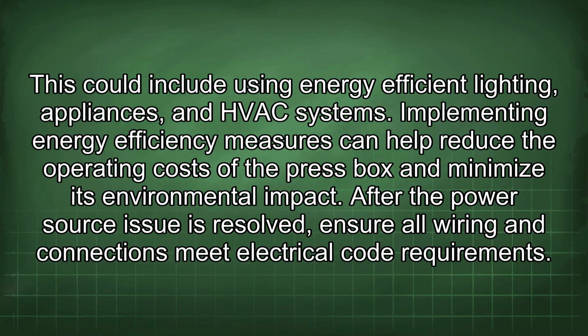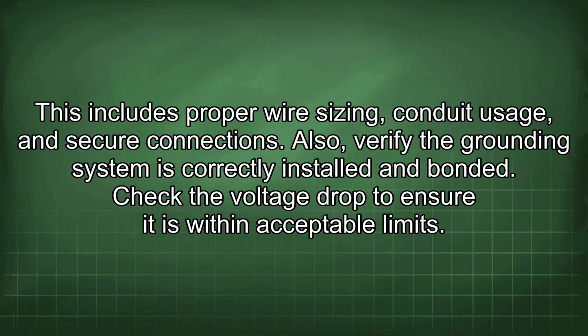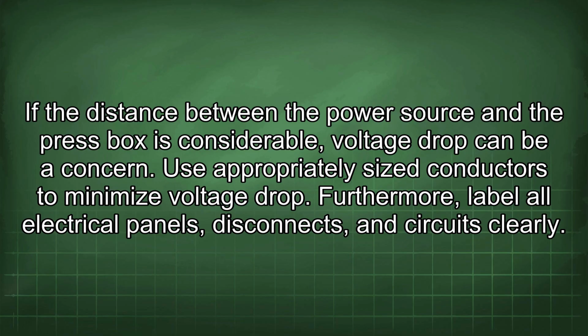After the power source issue is resolved, ensure all wiring and connections meet electrical code requirements. This includes proper wire sizing, conduit usage, and secure connections. Also, verify the grounding system is correctly installed and bonded. Check the voltage drop to ensure it is within acceptable limits. If the distance between the power source and the press box is considerable, voltage drop can be a concern. Use appropriately sized conductors to minimize voltage drop.